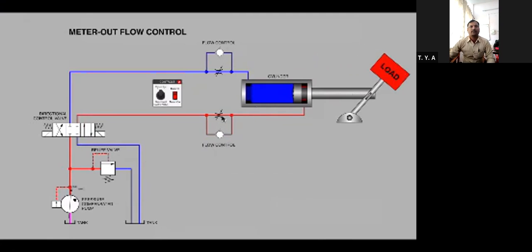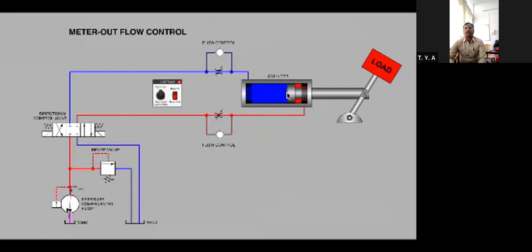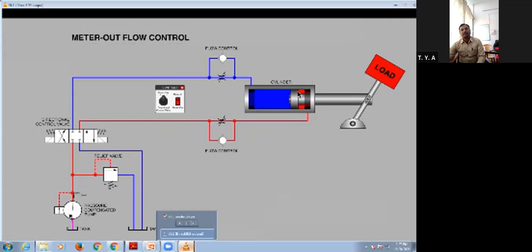This particular line here can become pressured to many multiples of what the pressure is on the backside of the cylinder. And exactly what that multiple or ratio is a function of the surface area difference between the back of the piston and the rod side piston, the annular or washer ring piston on the rod side. So that's a topic for another video, but keep in mind that meter out is not always a perfect scenario either.